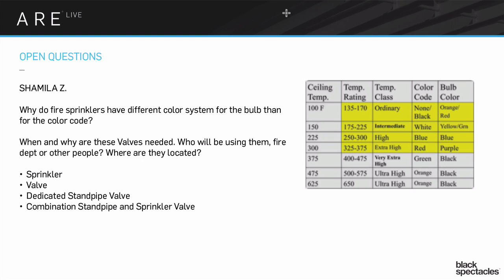Most places, individual heads go off when there's a problem. But in certain places, when there's a problem anywhere, all the heads go off. The classic example is an airplane hangar — there's a lot of fuel around and they don't want any fire to get out of control, so all the heads go off at once. Those are deluge systems.